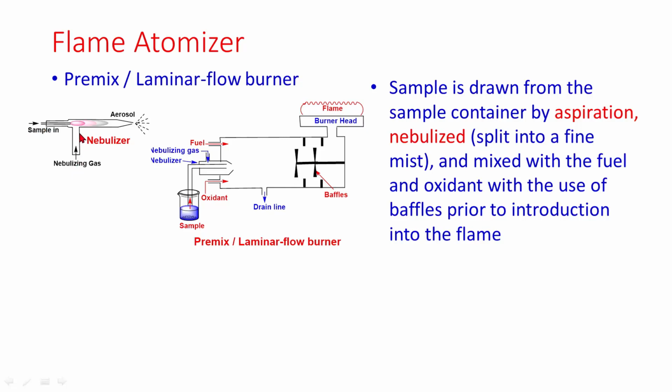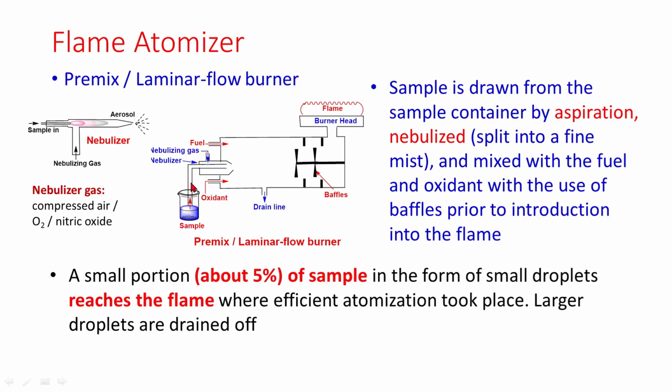There is a nebulizing gas and aerosol is generated. Nebulizer gas can be compressed air, oxygen, or nitric oxide. A small portion, about 5% of the sample in the form of very fine droplets, reaches the flame where efficient atomization takes place.